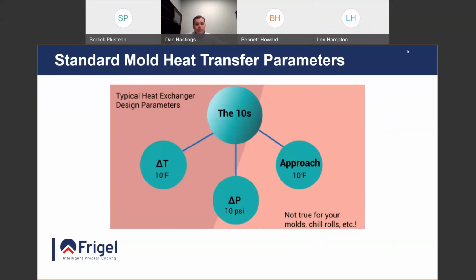A 10 psi pressure differential across the mold could be right if you're just considering the mold, but if you consider all the manifolds and hoses, I go into a lot of facilities where I see a lot of undersized 1/4 inch, 3/8 inch hoses, which may not be properly sized for a tool. Maybe on a small tool, but on a big tool, you see tons of these hoses, and they just absorb the pressure. They steal it from the mold, and if we increase our pressure drop, we're decreasing the flow rate to the unit. Quick connects are another one that just rob the tool of proper flow, creating a huge pressure drop and reducing the amount of flow going through it.